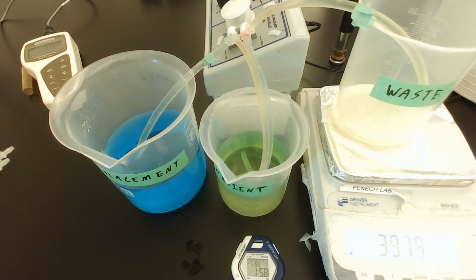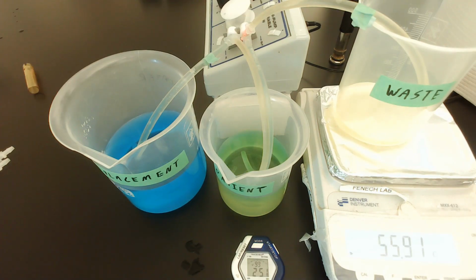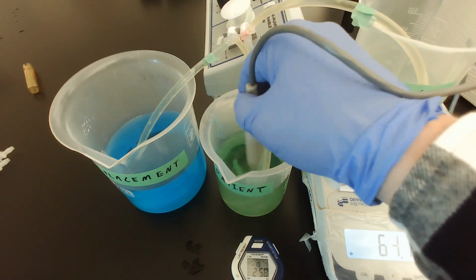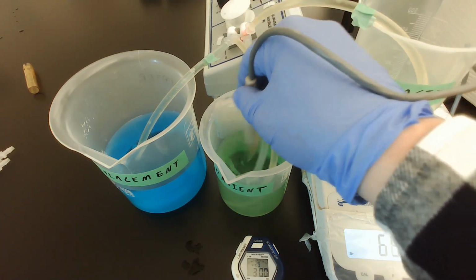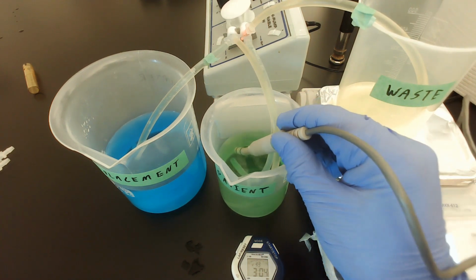And if we measure this over time, 1 gram is roughly 1 ml, so we can measure the mLs per minute, which gives us a speed of our pump. And so in this case, I'm just going to take 3 measurements, 1 at each minute, and this will give us a good average of the pump speed.